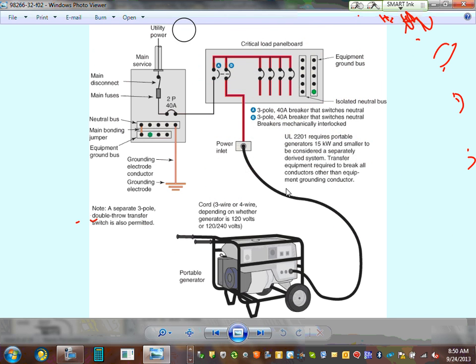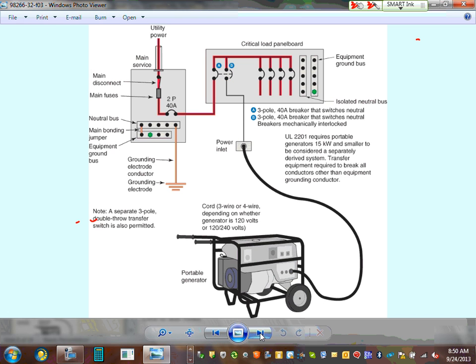So that's one step above just a plug. Now you have a power outlet, you plug it in, and you power a sub panel. That's the next step, powering it through a sub panel. You can see right now everything is running on the generator. You see that red stuff? Everything's running on gen. Now if you go run on utility, look at that. Now the power is coming through the utilities. So under normal operating condition, your load will be powered from the utility this way. Can you guys see that?